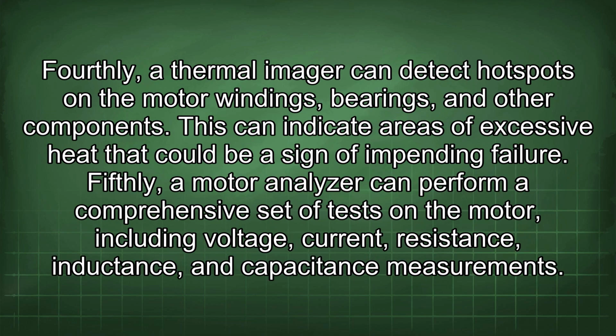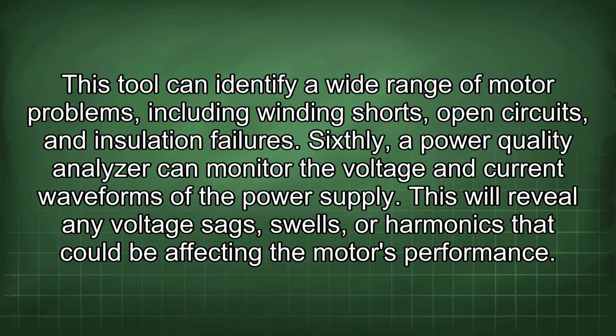Fourthly, a thermal imager can detect hotspots on the motor windings, bearings, and other components. This can indicate areas of excessive heat that could be a sign of impending failure. Fifthly, a motor analyzer can perform a comprehensive set of tests on the motor, including voltage, current, resistance, inductance, and capacitance measurements. This tool can identify a wide range of motor problems, including winding shorts, open circuits, and insulation failures.